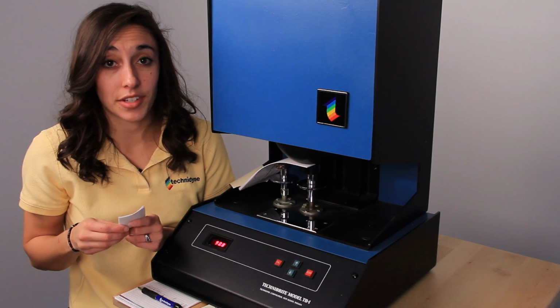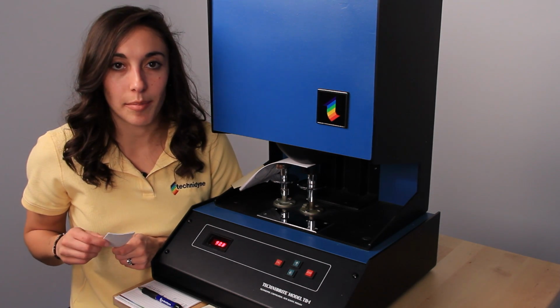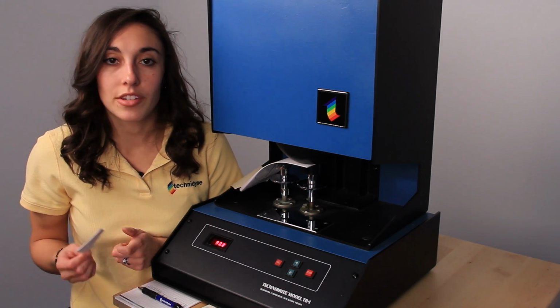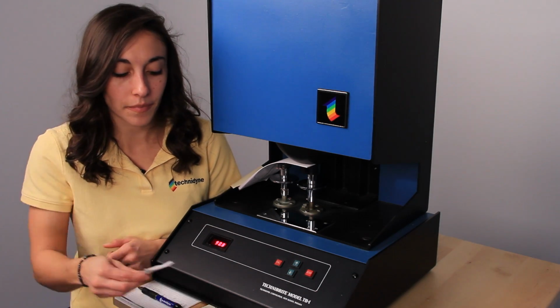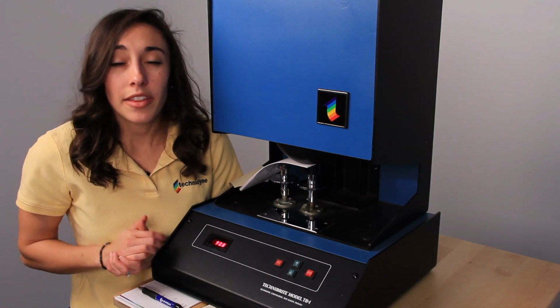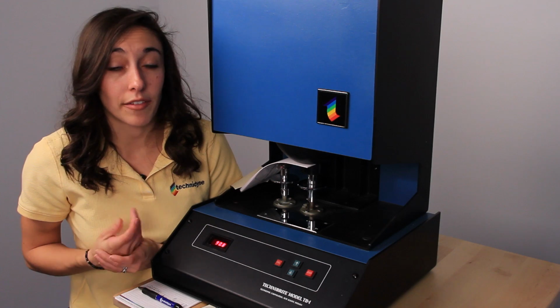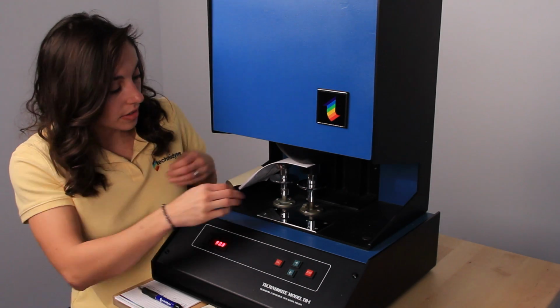Now ours already matches, so I'm going to go on to the last step, which is to calibrate the instrument to the working standard for daily use. It's important to remember that you're going to use the working standard every day as opposed to the primary standard.